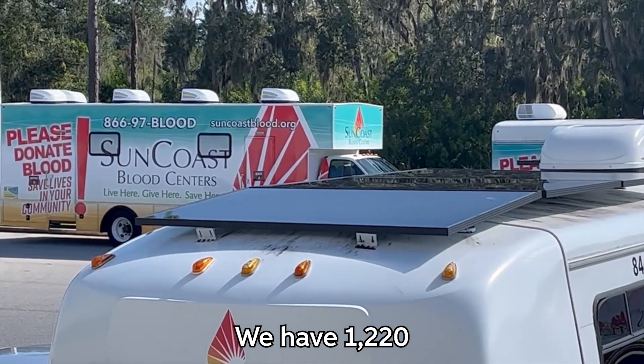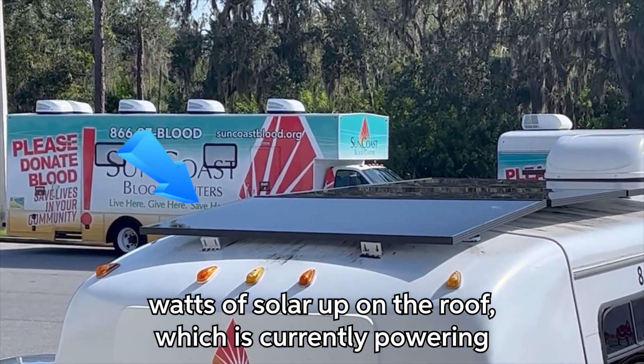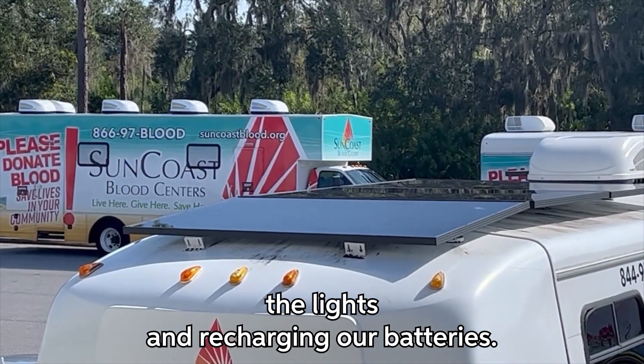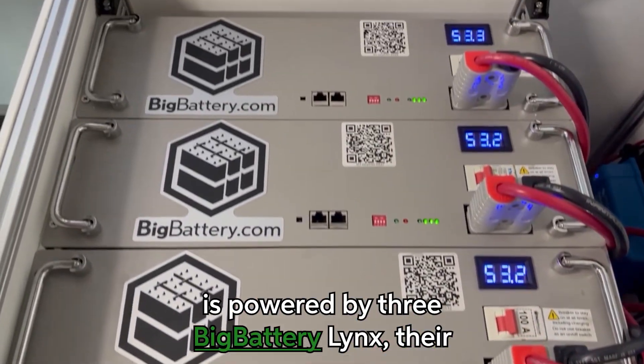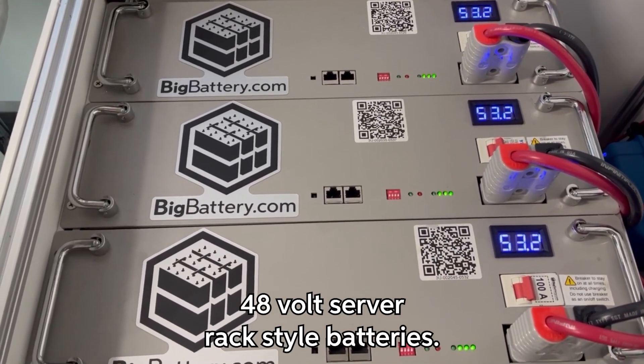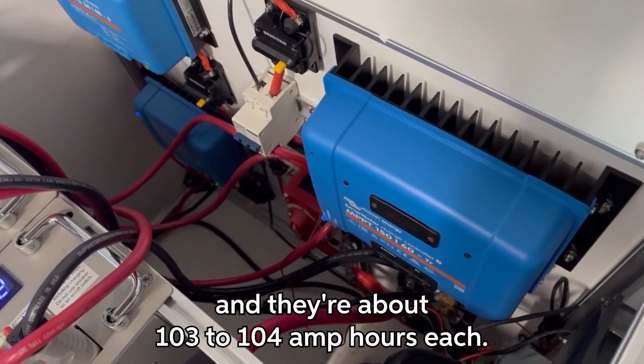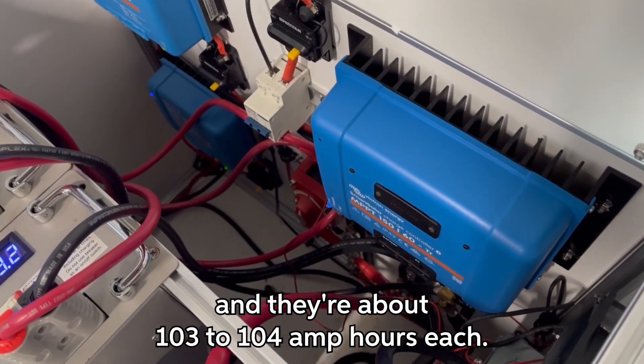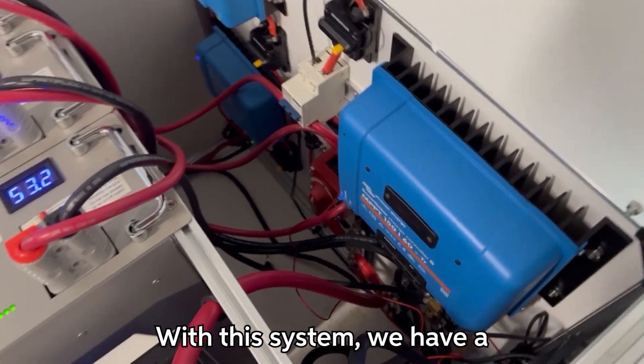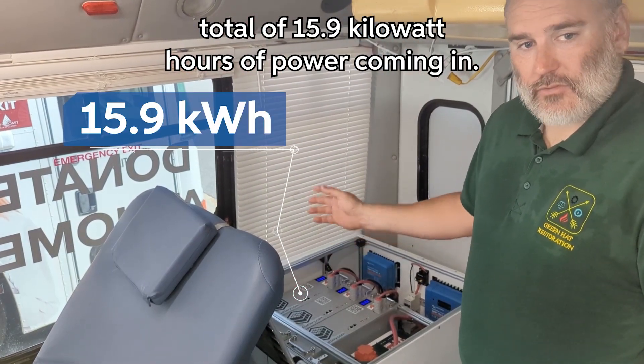We have 1220 watts of solar up on the roof, which is currently powering the lights and recharging our batteries. Our power supply system here is powered by three BigBattery Lynx — they're 48 volt server rack style batteries. They weigh about 100 pounds each and are about 103 to 104 amp hours each. With this system we have a total of 15.9 kilowatt hours of power.